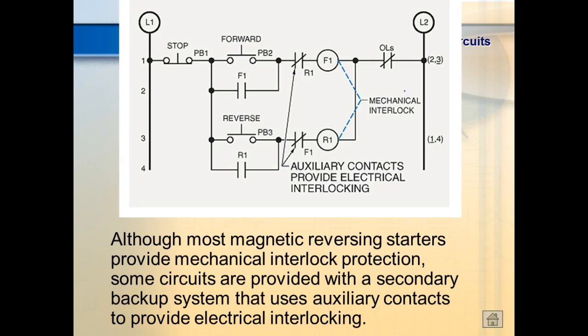This would be what we're going to look at. This is the ideal situation where you have both electrical interlock and mechanical interlock. We don't have a reverser for this code, so we're going to use two magnetic motor starters. We're not going to have a common overload, so our motor starters don't have this, and we're not going to connect that wire right there because we don't have a common overload for both of our motors.